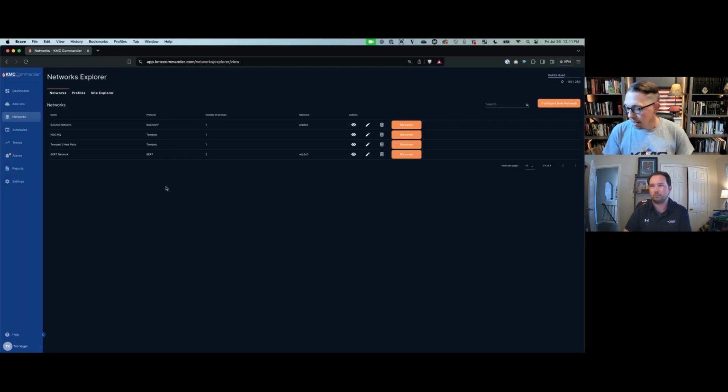Next step is you want to make sure that even before you get to the site, you've already talked to IT, but you also want to make sure that the gateway is set up and ready to go. Because we're doing updates so often, once or twice a month, there's a new gateway update. It's always good to plug it into the internet in your office, make sure it's updated and ready to go before you take it out to the site. And you could also then license it. When you buy a license, you have to tell the gateway, this is the license I want you to use, and this is the project I want you to point to. And once that is done in your office, you can unplug it and now take it to the job site.